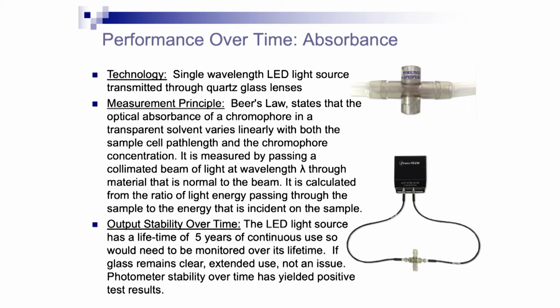And just to touch on the fact, we use an LED light source. It has a lifetime of 5 years or more. So it's ideally made for continuous processing without worrying about failures or heat up, et cetera, over time. So as long as the glass remains clear, you should be getting the same measurement. The top picture shows the flow cell, then you can connect to fiber optics and there's glass in the wall, so the instrument never touches the flow path, only the flow cell, including the glass on the wall.